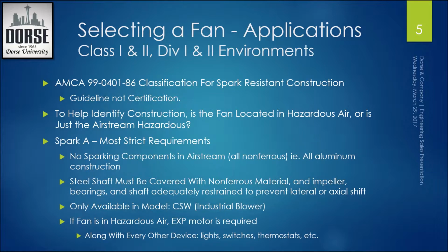So in order to help select a fan with the construction you need, it's helpful to know, is the fan in the hazardous air, meaning that the motor is also in the hazardous air, or is it only the airstream that's hazardous and it's passing through the fan? For example, maybe an inline fan versus a utility set, the motor can be out of the airstream in a utility set, it can in an inline fan as well. But those types of things determine what the motor needs to be rated for and what the fan needs to be rated for. So spark A, it's the most strict.